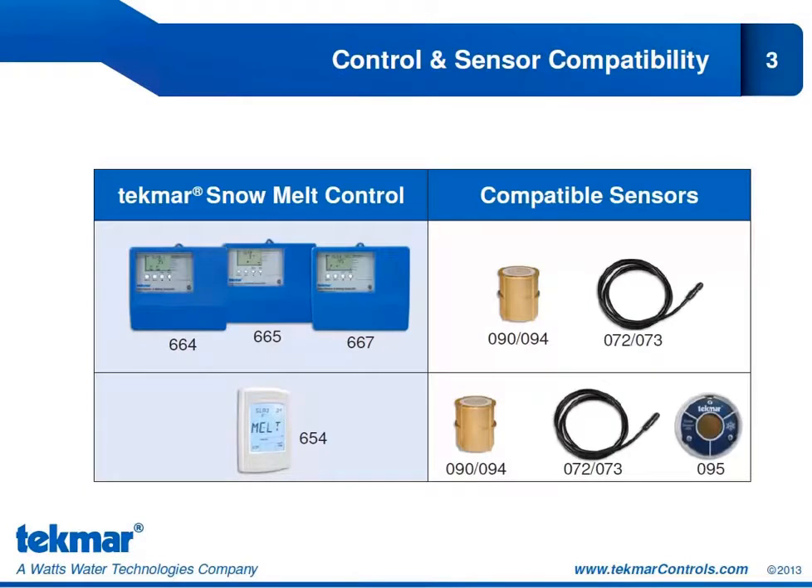This chart shows the tekmar snow melt controls we have available and which sensors are compatible with those snow melt controls. On the top left-hand side you can see the 664, 665, and 667. These snow melt controls are compatible with the snow ice sensor 090/094. You could also choose to connect them to the 072 or 073 slab sensor.